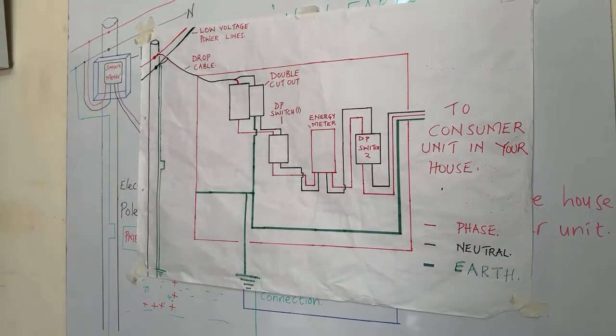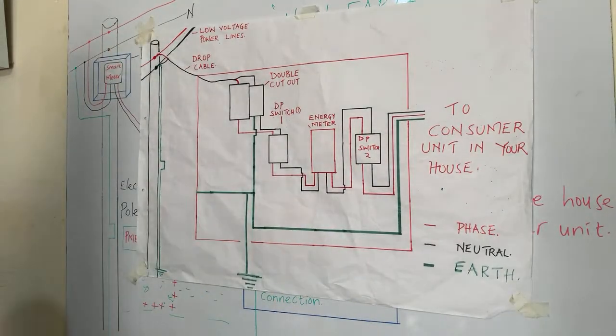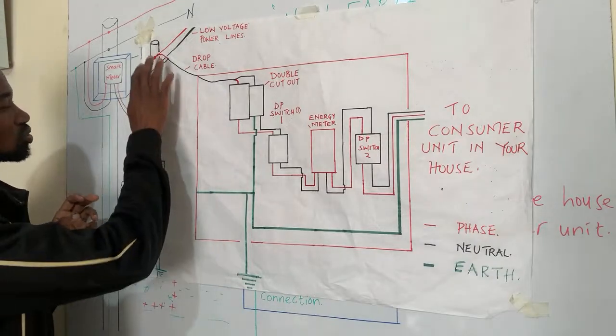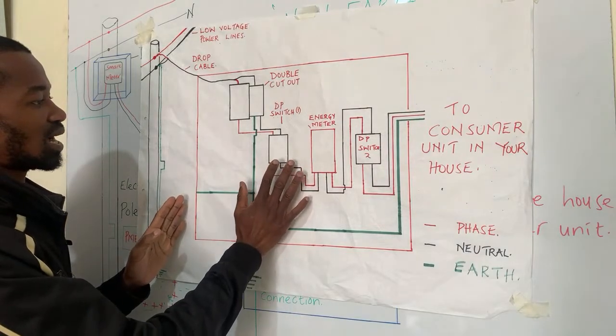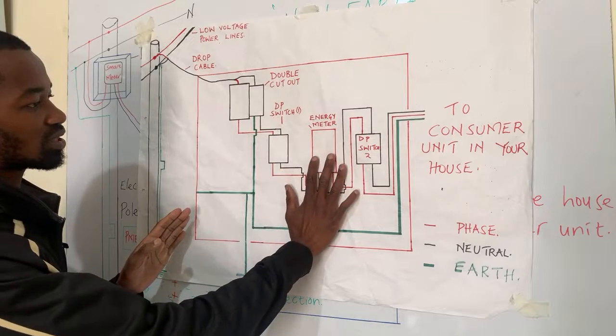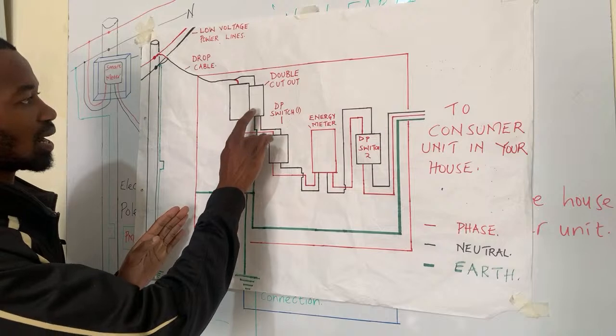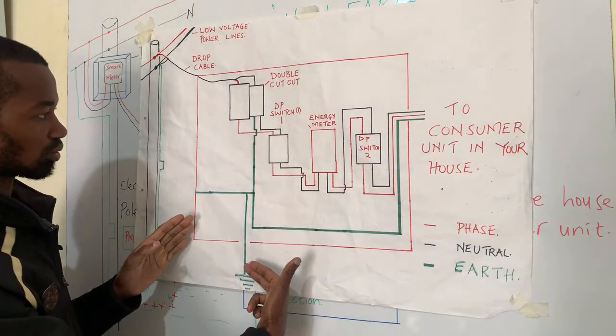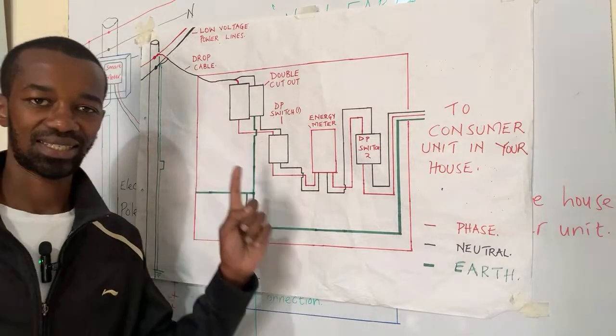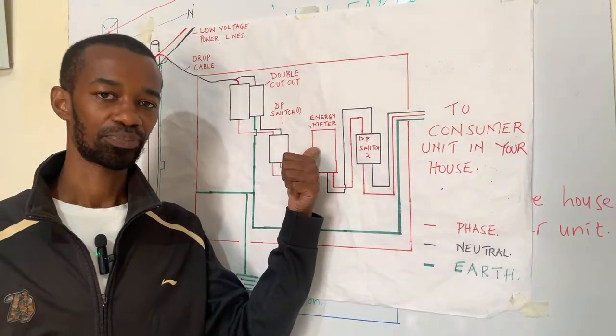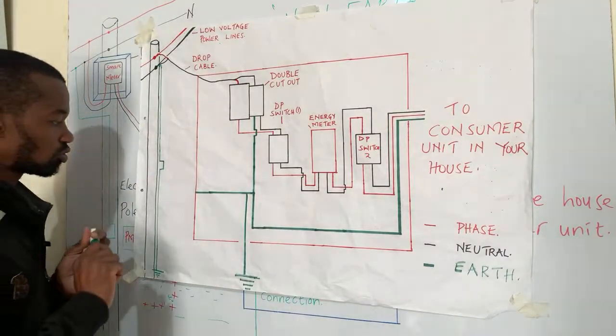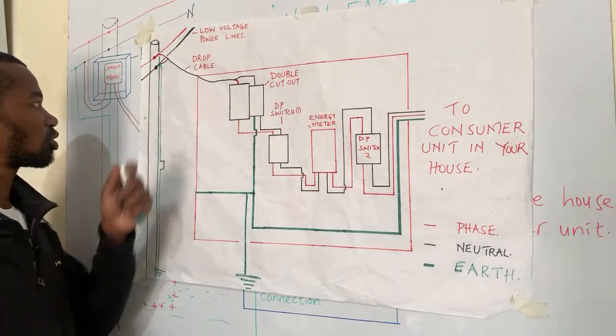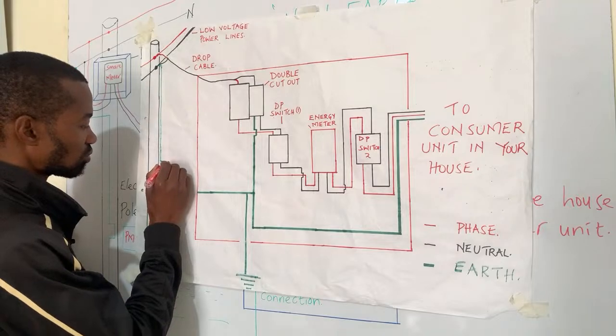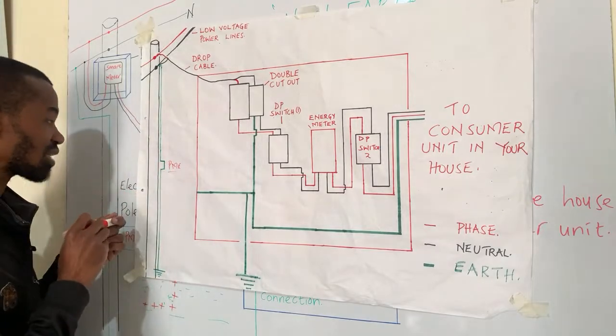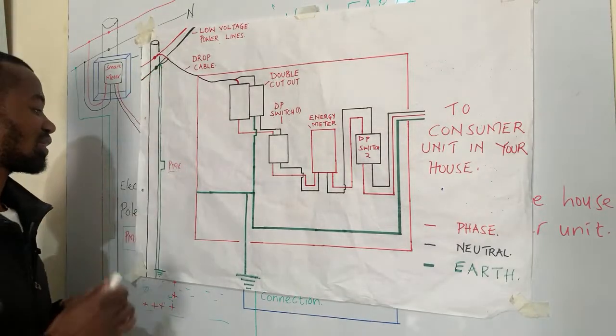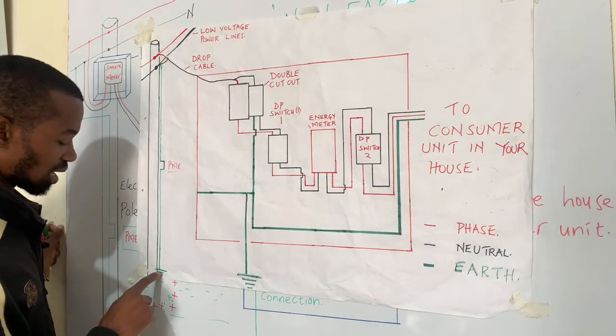Yes. So this one is to just show you that in case you have a setup whereby the meter box is housing the meter as well as the cutout and everything else, the bond is happening at the cutout, where you have the earth connection being bonded with the neutral. But the key point is that it is before the energy meter. So again, at that level, you need to understand that our PME is already done at the pole, the immediate pole that is serving the connection. This one will definitely be the PME, protective multiple earthing, that has been connected with the neutral. And then when it gets to this particular point, it is earthed on the ground.